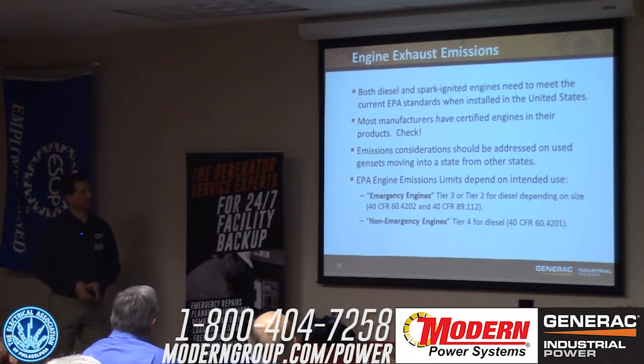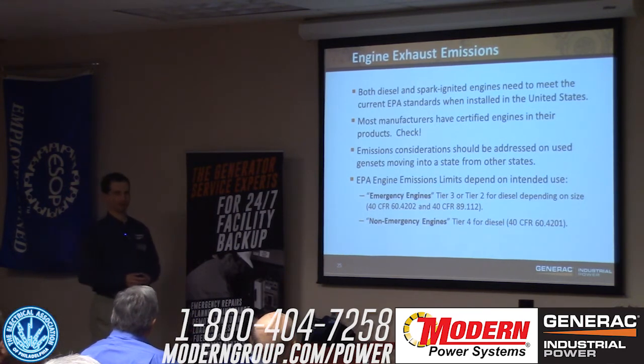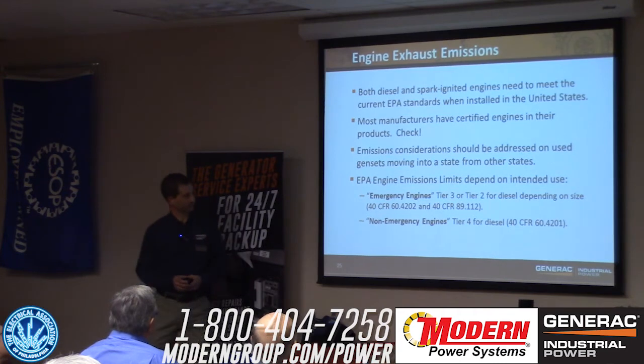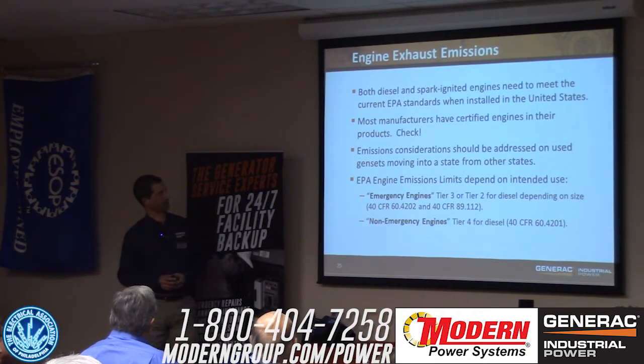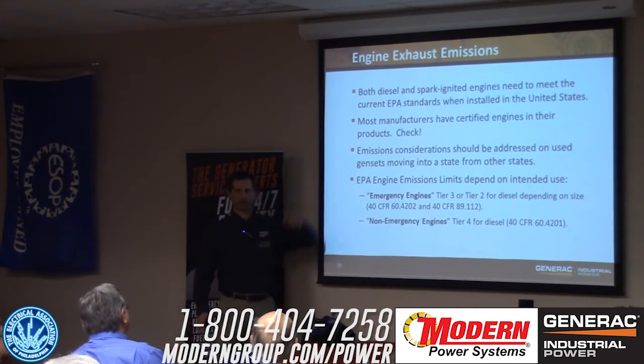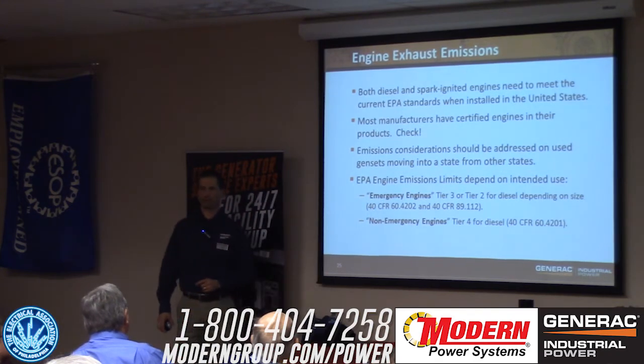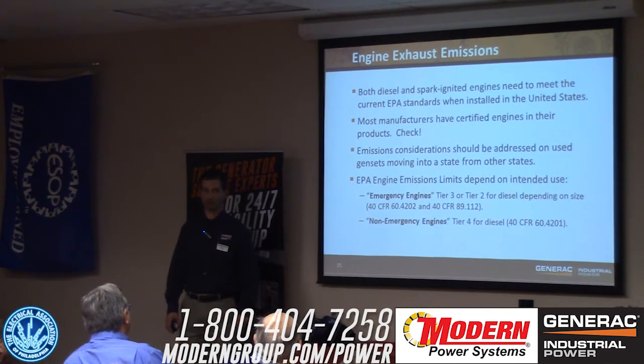In terms of exhaust, the EPA gets into the game too. We've got to meet EPA exhaust emissions requirements when these things go into service in the United States. Most manufacturers will have their products, or at least most of their products, EPA certified from the factory, but you have got to check. If that product rolls out and it's not EPA certified from the factory, when year 3 rolls around, it's got to be field emissions recertified.